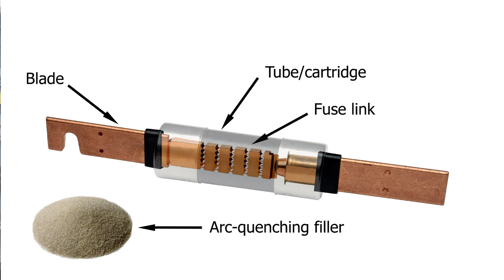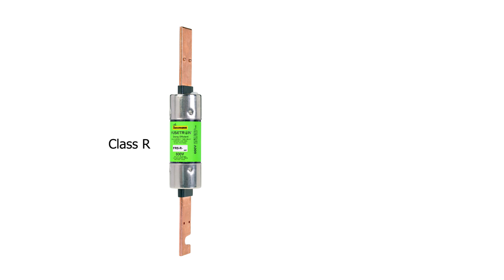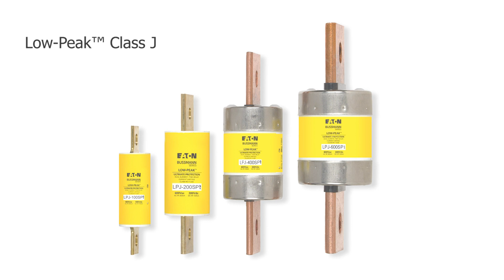Fuses have rejection features based on physical size or by a construction characteristic. A fuse of one class and case size cannot be installed in a different type of mounting. This ensures that the replacement fuse being installed will have the same voltage and interrupting ratings. One exception is that Class R fuses can be installed in Class H fuse mountings, offering an upgrade in protection. However, lower performing Class H fuses cannot be installed in Class R fuse holders. The Class J fuse is size rejecting and virtually eliminates installing the wrong fuse type with potentially lower performance characteristics.